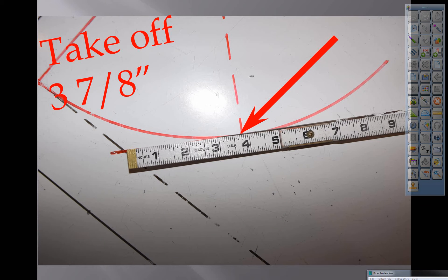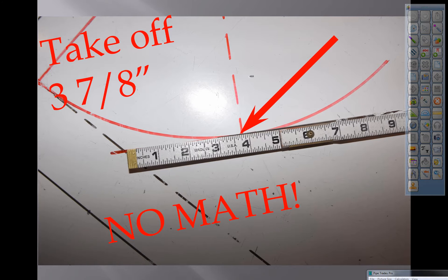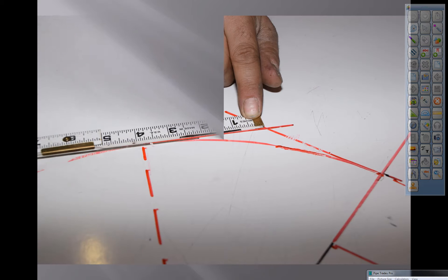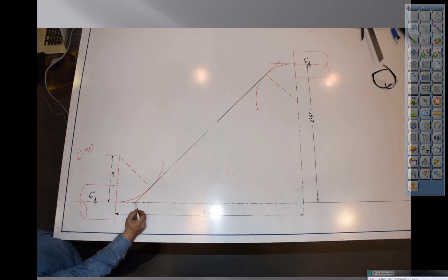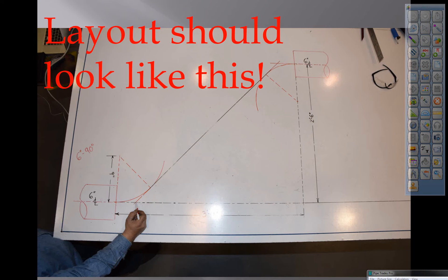Keep in mind we still don't know the angle of the fitting, but we do know that the fitting takeoff is 3 and 7 eighths, that will be cut out of a 6 inch long radius 90 and so far we have used no math. We're going to verify the other end at 3 and 7 eighths. Right now your layout should look like this.